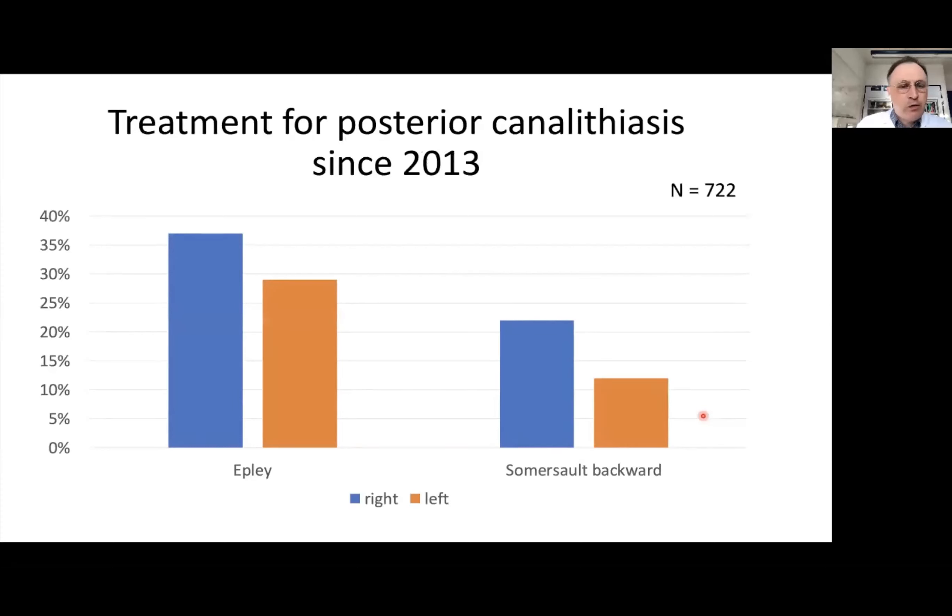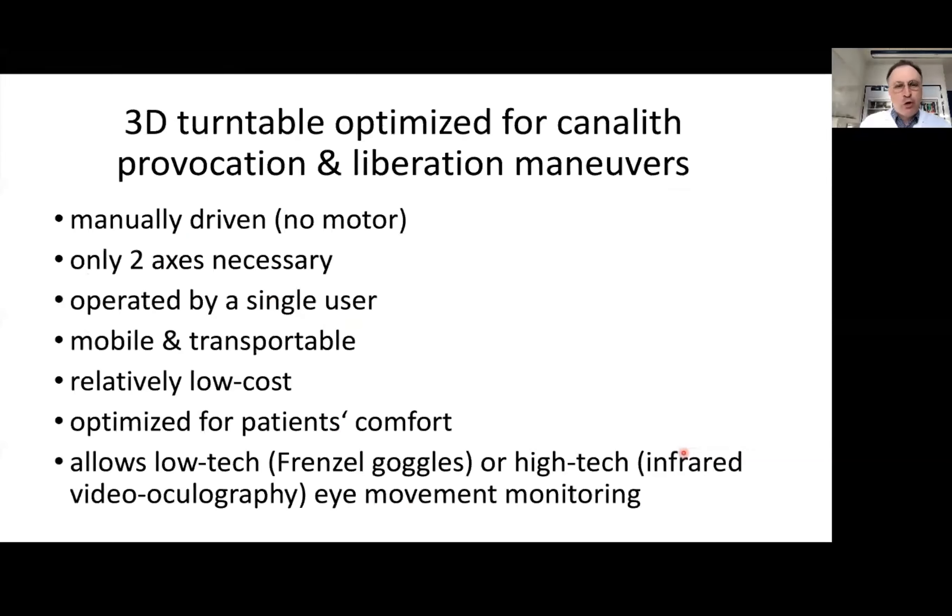For posterior canalithiasis, we mainly used the Epley maneuver and more rarely the somersault backward maneuver. Motorized turntables are very rare and expensive, so we began thinking about developing a turntable with the same capabilities for provocation and liberation of BPPV, but manually driven without a motor. We determined that three axes are not necessary — two axes are sufficient — and it should be operable by a single user.